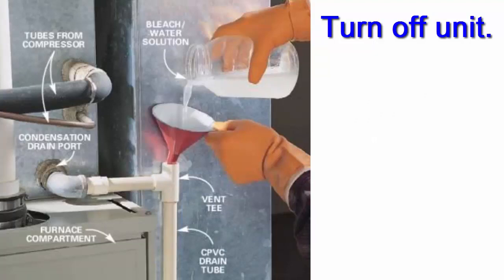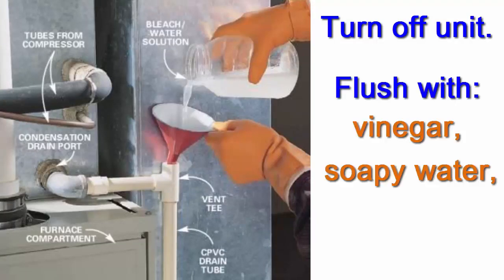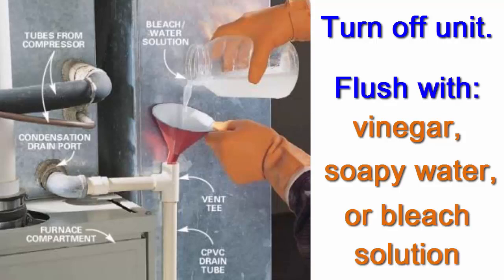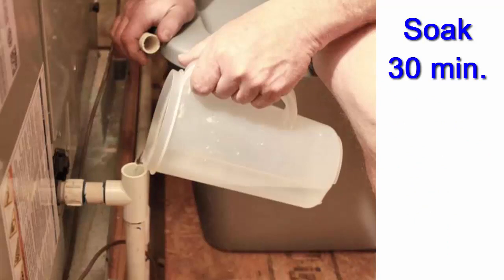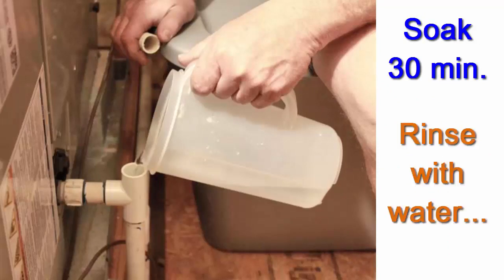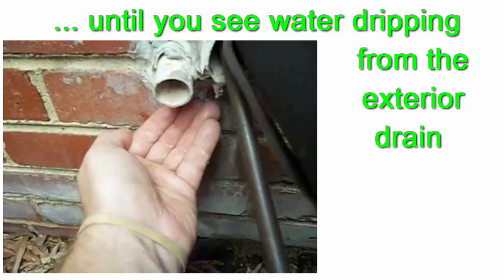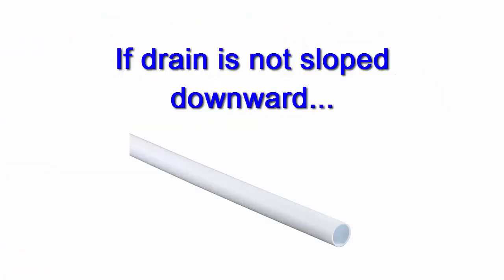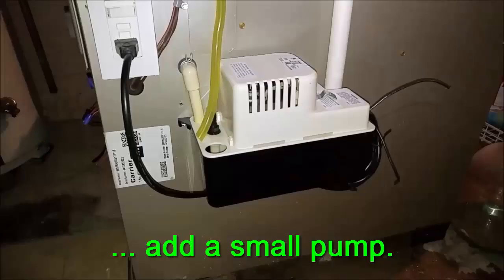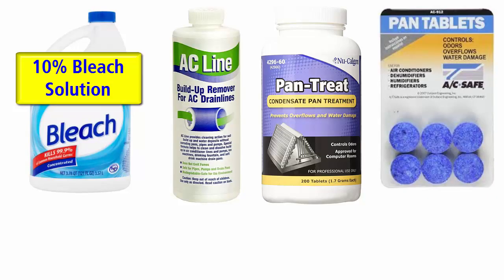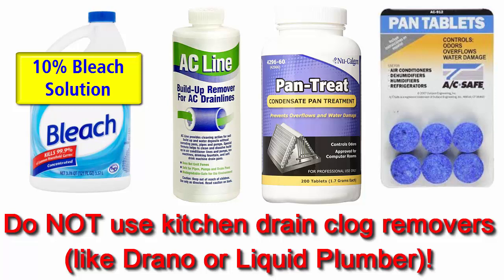With the system turned off, flush out the drain using distilled vinegar, hot water with mild dish soap, or a 10% bleach solution. Leave the solution to soak for up to 30 minutes. Then rinse the lines with clean water. Be sure you can see the water exiting freely out the exterior condensate line. If the drain line does not have a direct downward slope, allowing it to make use of gravity to help the water exit, you may need to have a small pump added to help push the water out. If there is a reservoir which holds water until it exits, you may need to add a mild bleach solution, condensate drain line cleaner, or anti-algae tablets to the reservoir on a regular basis to prevent the growth of mold and algae.